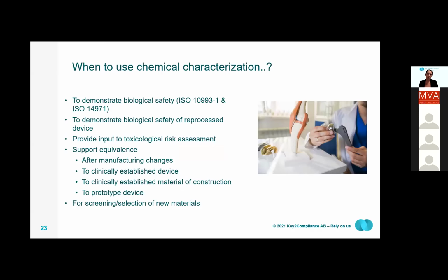So when can I use chemical characterization? Well, of course, as a very basic tool to demonstrate the biological safety in line with both the ISO 10993 series and the overall risk management standard. You can use it to demonstrate the biological safety of a reprocessed device, and you can use it to get input to the toxicological risk assessment.